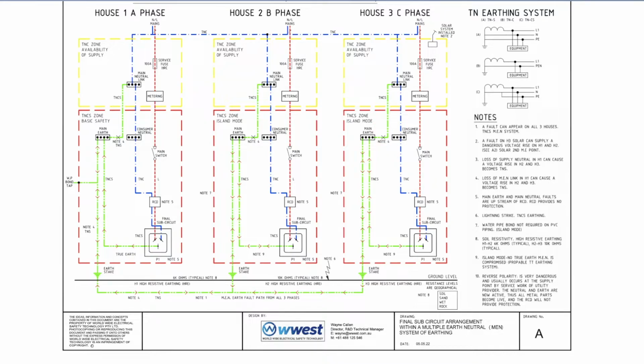Which then, if we go over to here and look at our notes, we can see that note 1 says a fault can appear on all 3 houses through the TNCS earthing system, which is the M.E.N system. Because as you look down here, you can see that the earth stakes are in the ground. And so a fault here could travel across this earth path, back up this one. See the arrow there? It's pointing up. It can go back up to the neutral link, up through there, all the way back up to your main neutral. And it's exactly the same with all 3 houses.